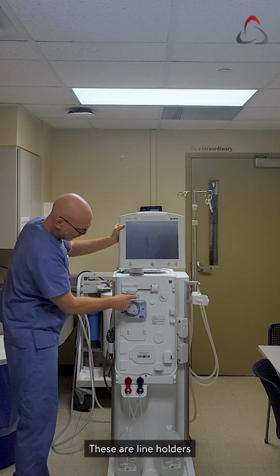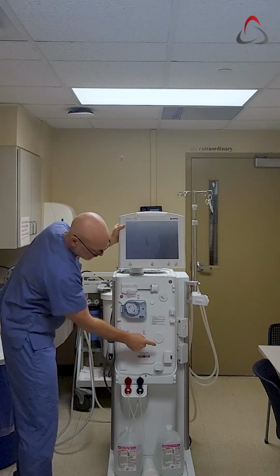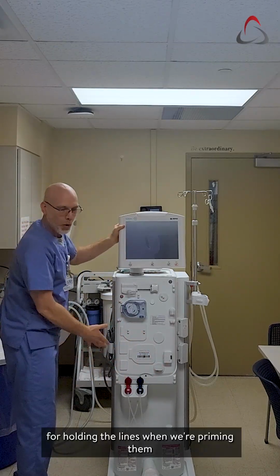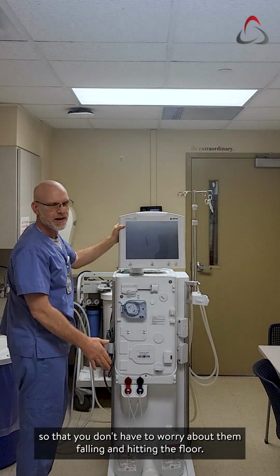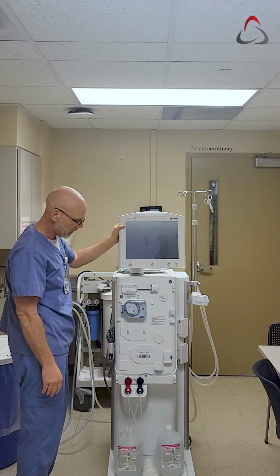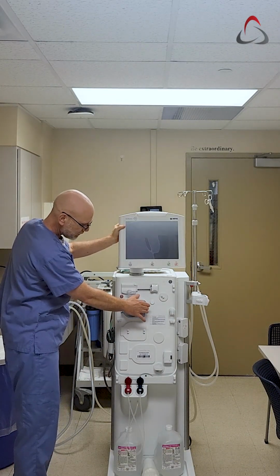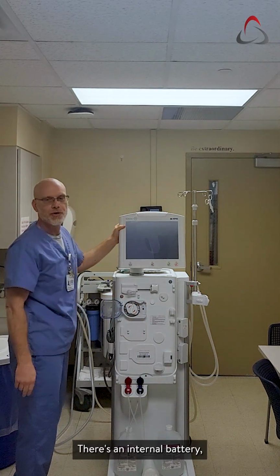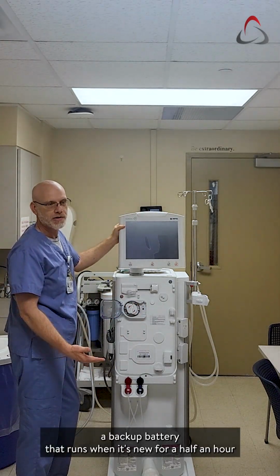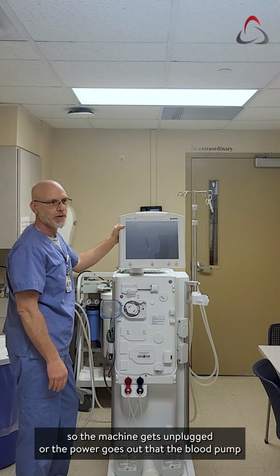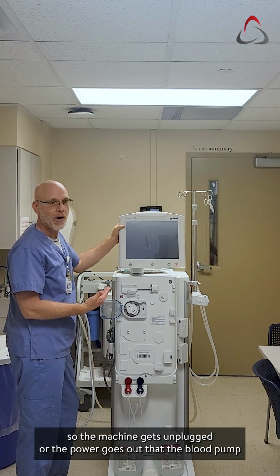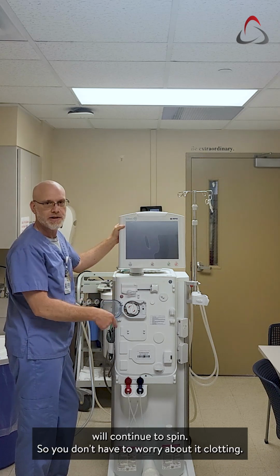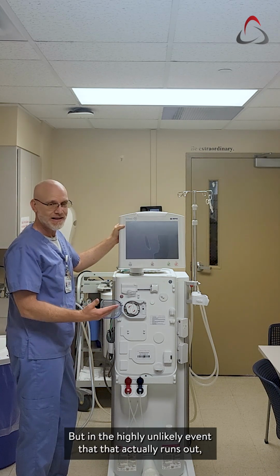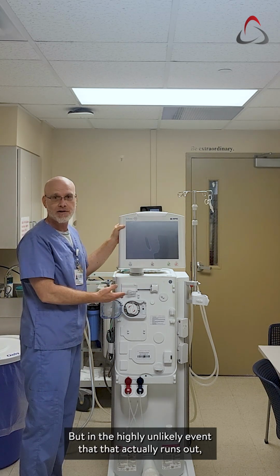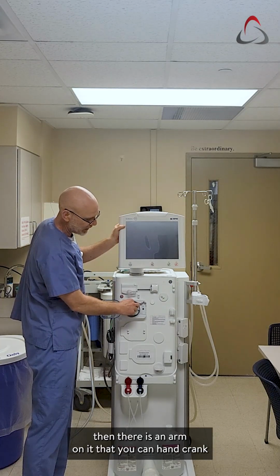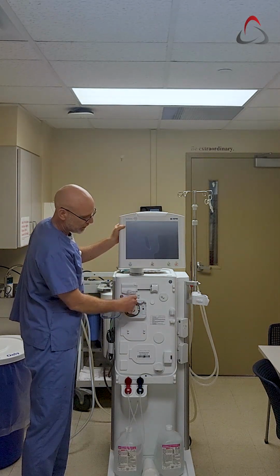These are line holders for holding the lines when we're priming them so that you don't have to worry about them falling and hitting the floor. The blood pump. There's an internal battery, a backup battery, that runs when it's new for a half an hour. So if the machine gets unplugged or the power goes out, the blood pump will continue to spin so you don't have to worry about it clotting. But in the highly unlikely event that that actually runs out, then there is an arm on it that you can hand crank the blood pump.